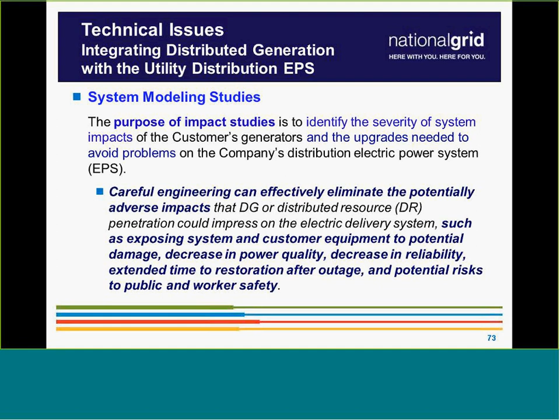One thing we find when interconnecting smaller projects is that even with a small project, either alone or combined with your neighbors, we start to overload transformers. When you overload a distribution transformer, you need to replace it with something bigger. We look at the nameplate rating, and if the DG exceeds it, we need to replace the transformer with something larger.